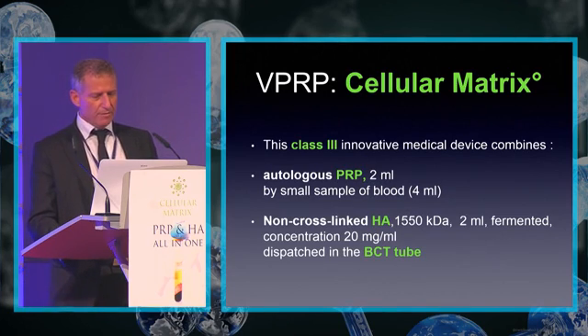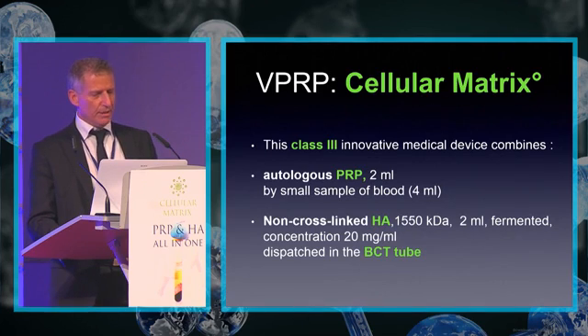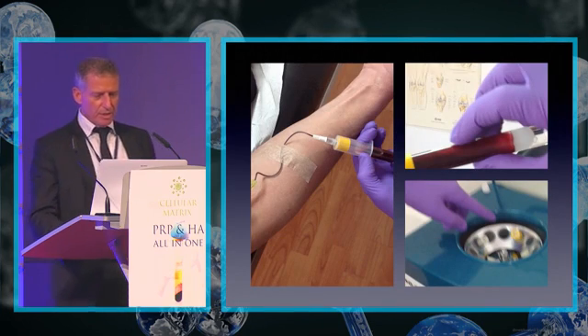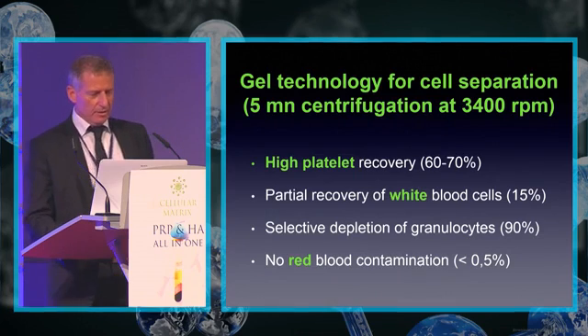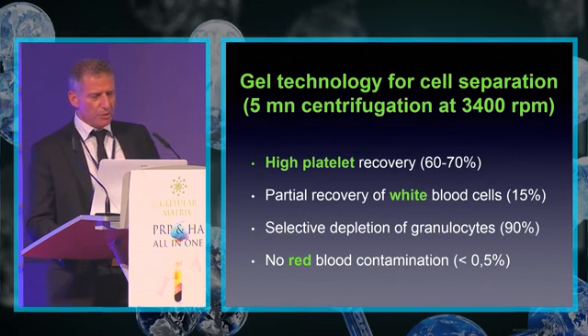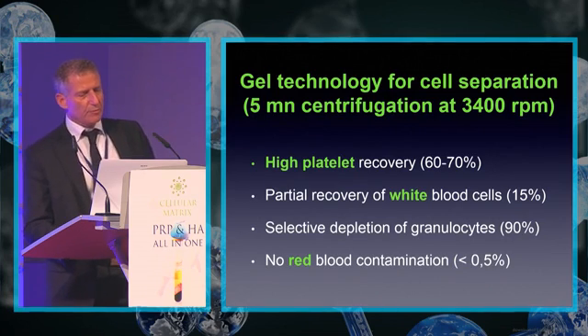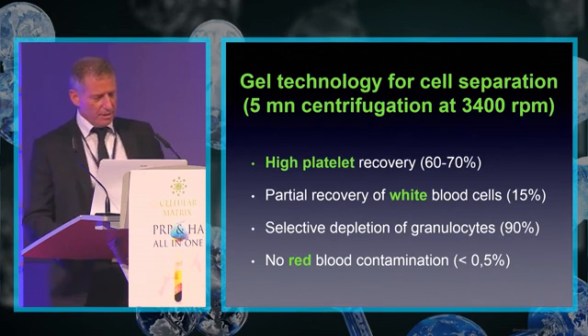The HA component is 2 mL, fermented, at a concentration of 20 mg/mL, dispensed in the BCT tube. The first step is blood sampling and centrifugation. Cellular Matrix uses gel technology for cell separation: 5 minutes centrifugation at 3,400 RPM.